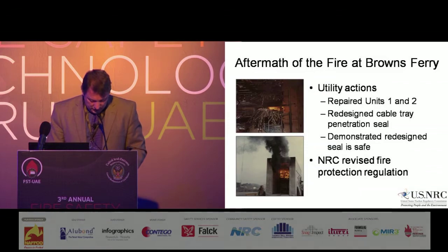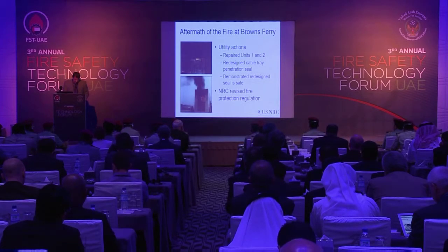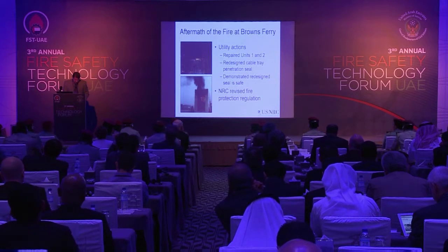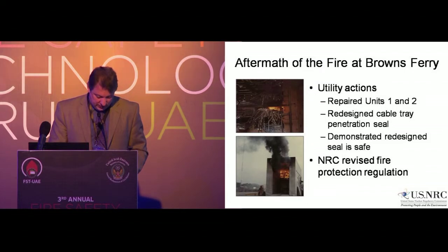Immediately following the fire at Browns Ferry, efforts began to assess the damage and repair Units 1 and 2. One of the biggest challenges for the utility was to redesign the cable tray penetration seal and prove to the NRC that the seal was safe. At the time of the Browns Ferry fire, however, no nationally recognized standards were available for fire testing of cable tray penetration seals. The utility constructed a full-scale model at the Watts Bar Nuclear Power Plant construction site and eventually successfully qualified the redesigned cable tray penetration seal and used this to justify the restart of Units 1 and 2 and used it as a licensing basis for Unit 3.